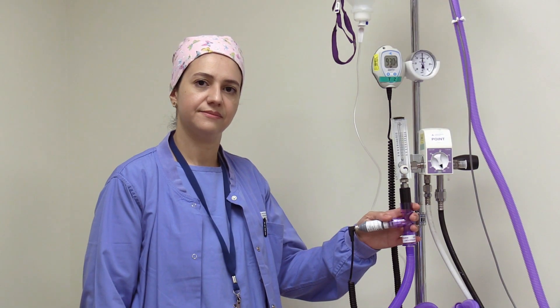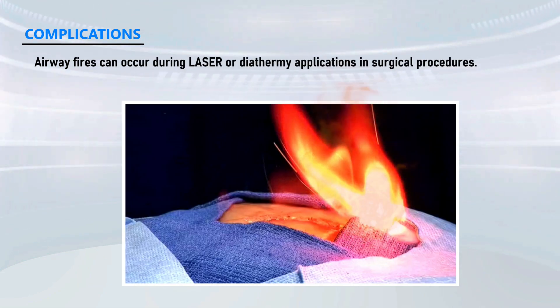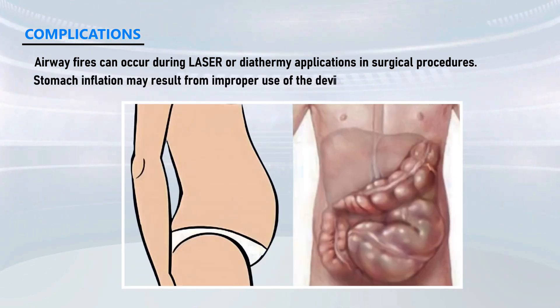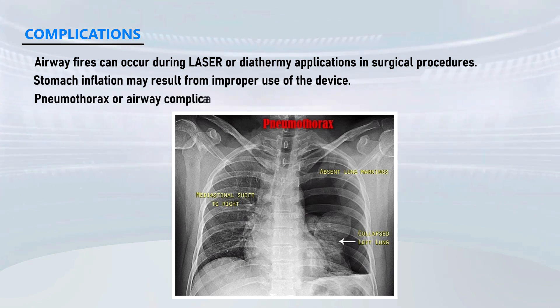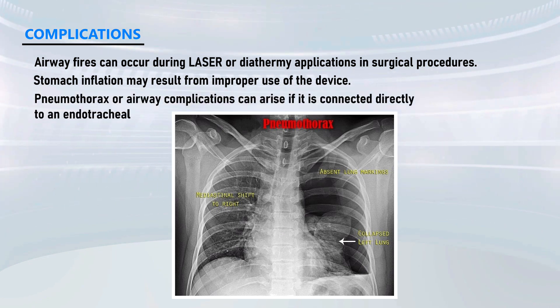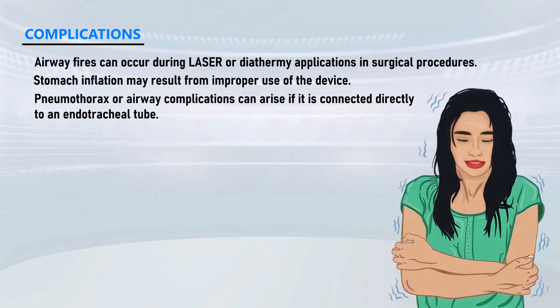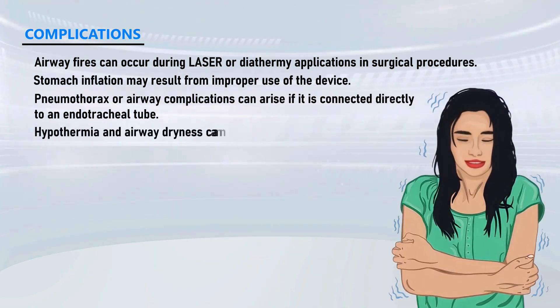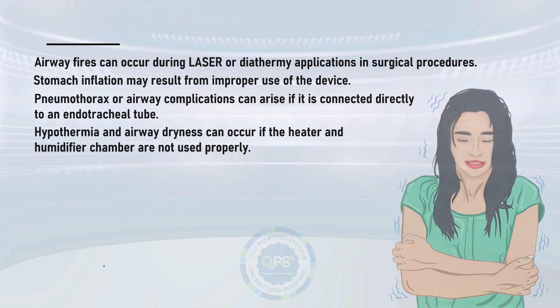Regarding complications: airway fires can occur during laser or diathermy applications in surgical procedures; stomach inflation may result from improper use of the device; pneumothorax or airway complications can arise if the device is connected directly to an endotracheal tube; and hypothermia and airway dryness can occur if the heater and humidifier chamber are not used properly.